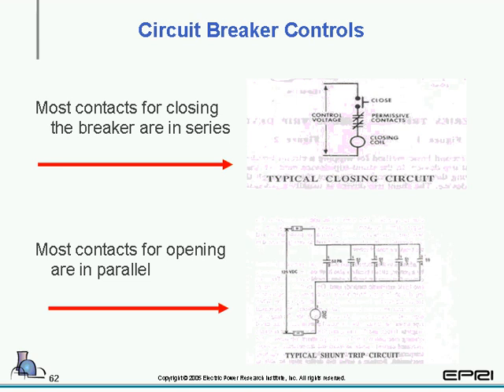Look at the electrical controls of a breaker. Most contacts for closing a breaker are in series and are known as permissive contacts. Most contacts for opening are in parallel, which you see these set of contacts can all feed, any one of them can feed this trip coil.